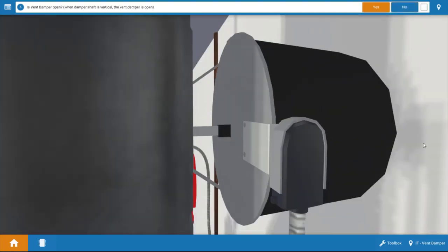Next, we need to see if the vent damper is actually open. Now, the vent damper closes off the flue passageway on the off cycle, preventing heated air from migrating up the draft hood or draft diverter and out of the space. And of course, this would lead to considerable heat loss.